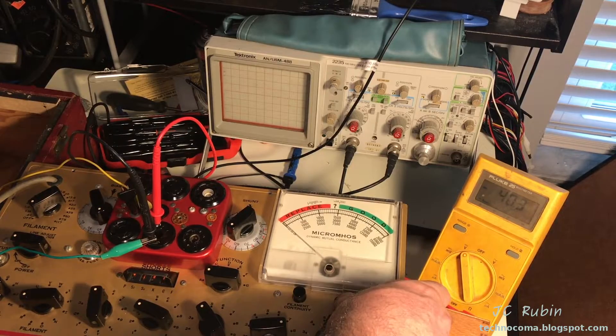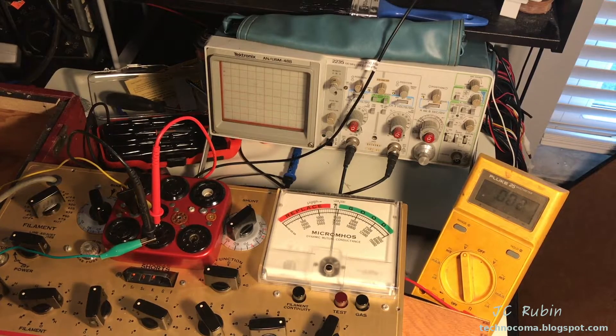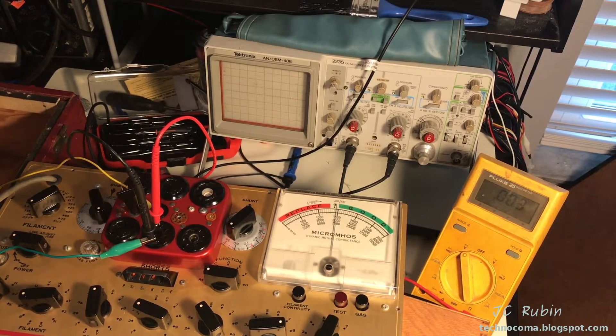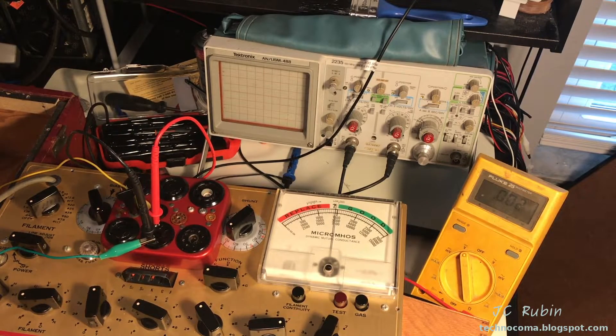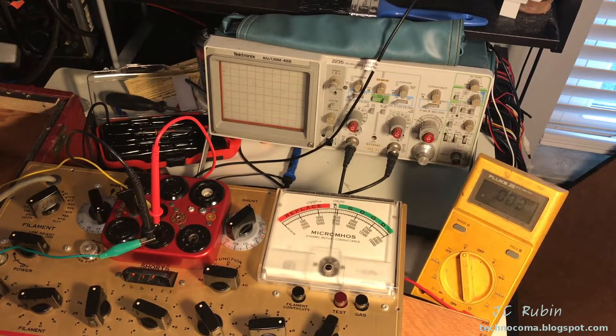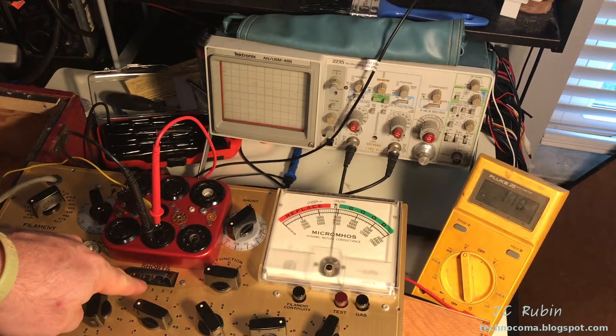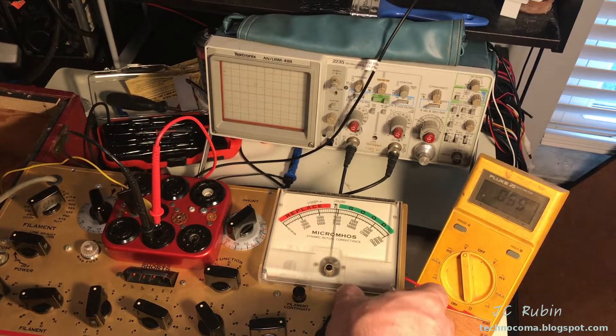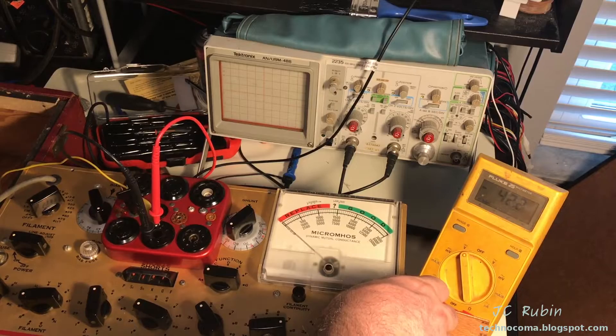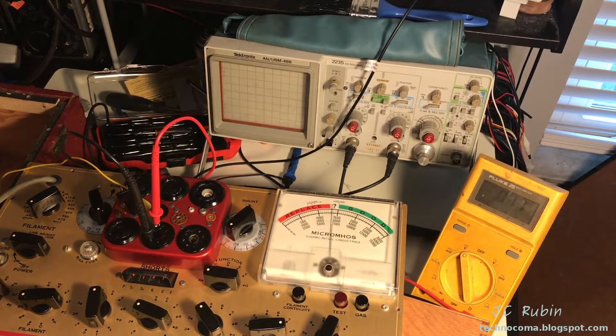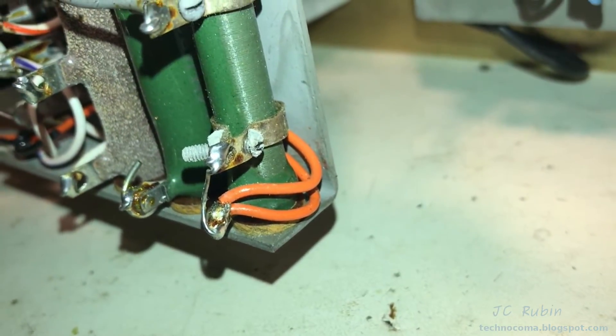I'm going to let go of the test button. That does not require any adjustment. What I am going to show now is what would be adjusted if this were not within 40 volts DC plus or minus two volts. I'm going to remove the shunt, which also relieved that short light. I'll hit the button again and show that without the shunt it shows 42.2 volts.